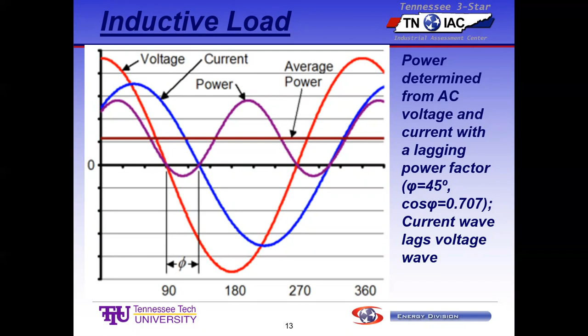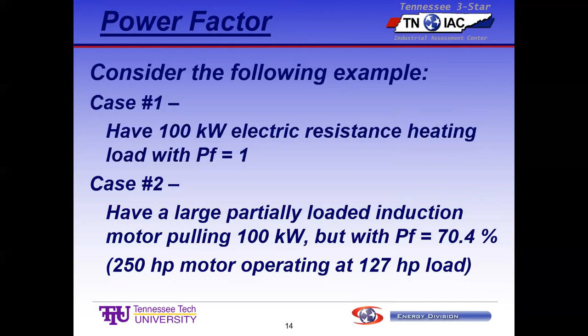Okay, and this has some real practical ramifications for us. In order to see what happens, I've made up a little example. Let's say we have a simple 100 kW load, and it's going to be a 100 kW load in both cases. For number one, it's an electric resistance heater, just a strip heater, pulling 100 kW. In case two, it's a lightly loaded 250 horsepower motor that's actually putting out 127 horsepower, and that translates into 100 kW of input power to the motor. So let's see what happens.